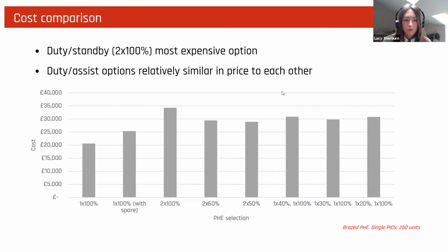I then looked at cost comparison. So as you might expect, the duty standby provided the most expensive option, and the duty assist options are relatively similar in price to each other. There wasn't one that was significantly more or significantly less expensive. This was for the brazed plate heat exchanger with a single PICV.